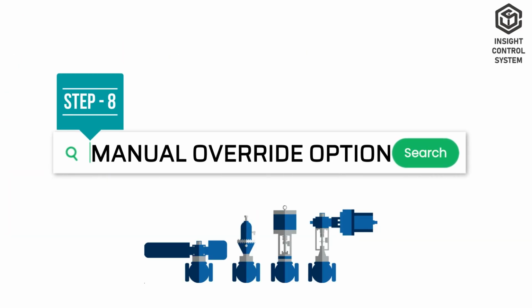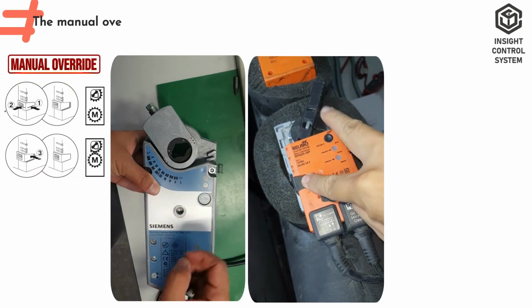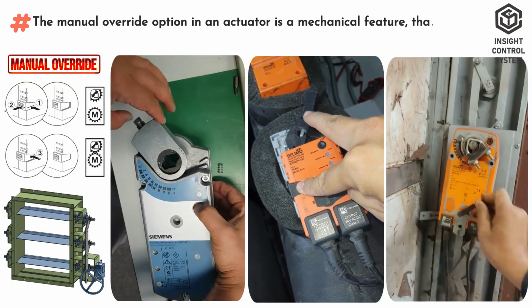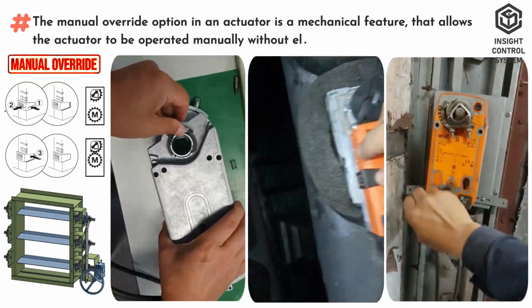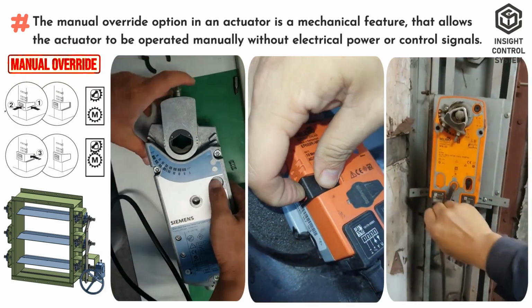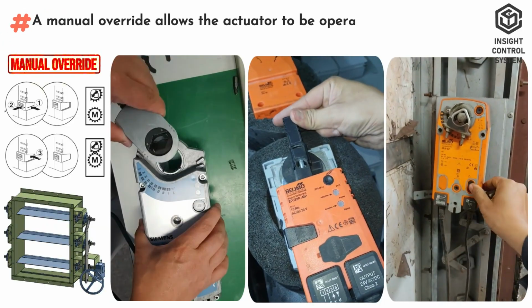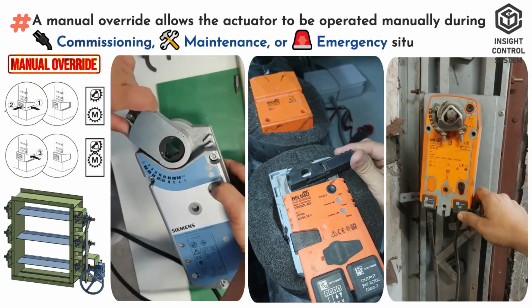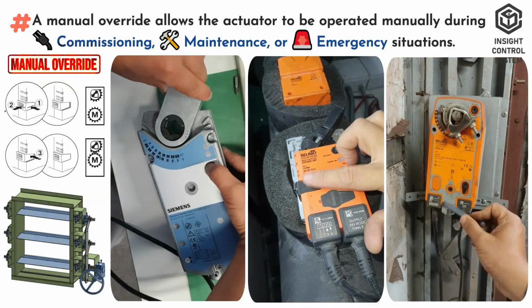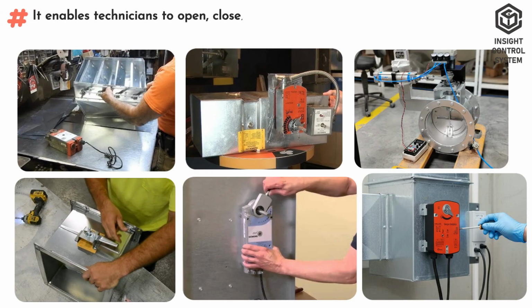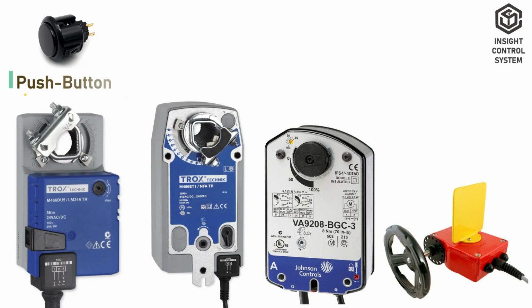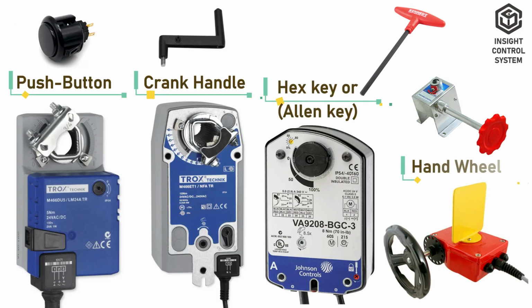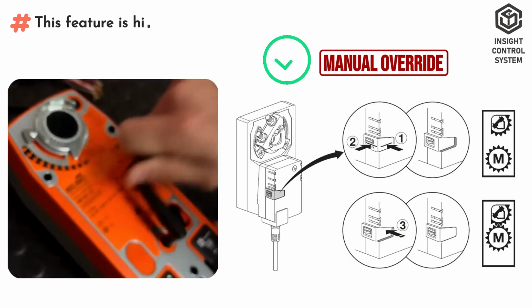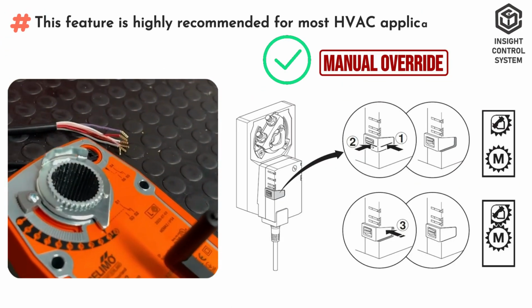Step 8. Manual override option. The manual override option in an actuator is a mechanical feature that allows the actuator to be operated manually without electrical power or control signals. A manual override allows the actuator to be operated manually during commissioning, maintenance, or emergency situations. It enables technicians to open, close, or position a damper or valve by hand, typically using a push button, crank handle, hex key, or Allen key hand wheel. This feature is highly recommended for most HVAC applications.